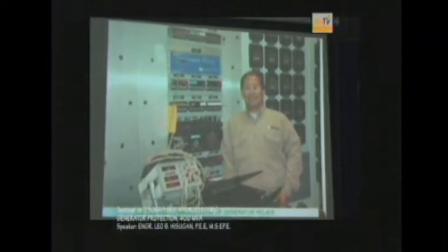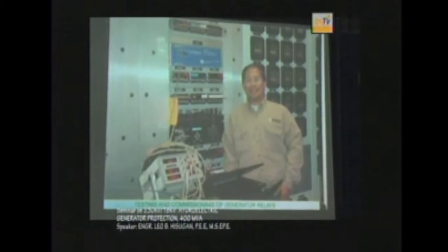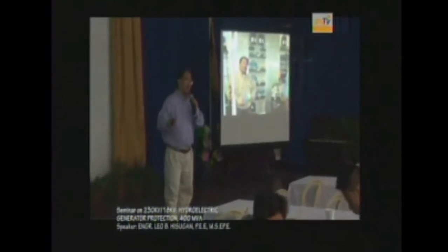Okay, next we were doing the final testing and commissioning of the relays. So what we have here is the set Bravo relays or set A relay, and this is a Schweitzer SEL 300G generator relays, and this one is, I think, the GE relays here. Okay, we have some motor relays here. These are some of the other differential relays and transformer relays here. So we're doing the final testing during the time and if you are the systems protection engineer that does all the relay settings and calculations, you have to go out in the field, provide all the testing fault files for you to validate all your settings and calculations are correct and it operates properly.